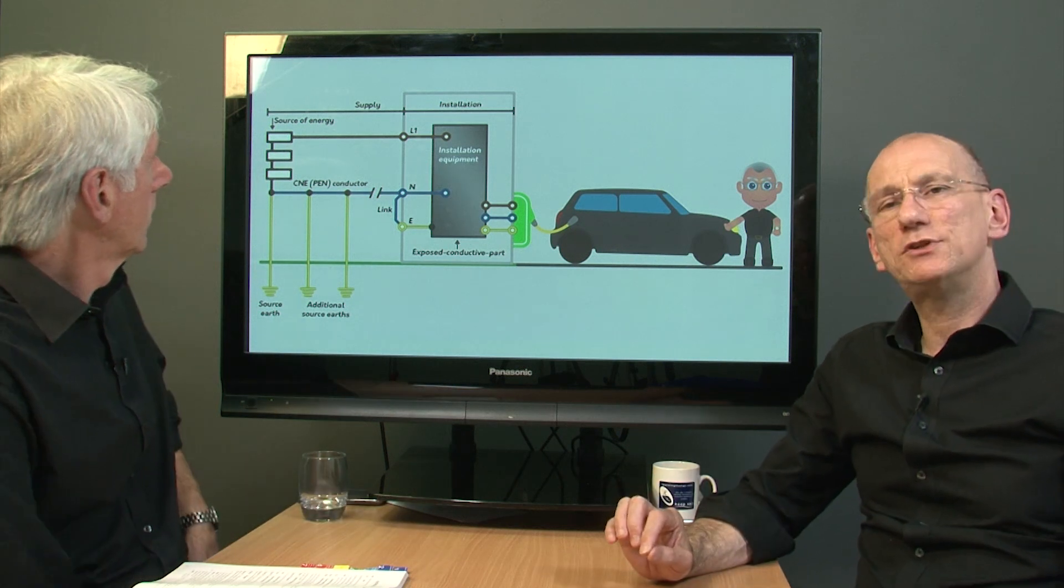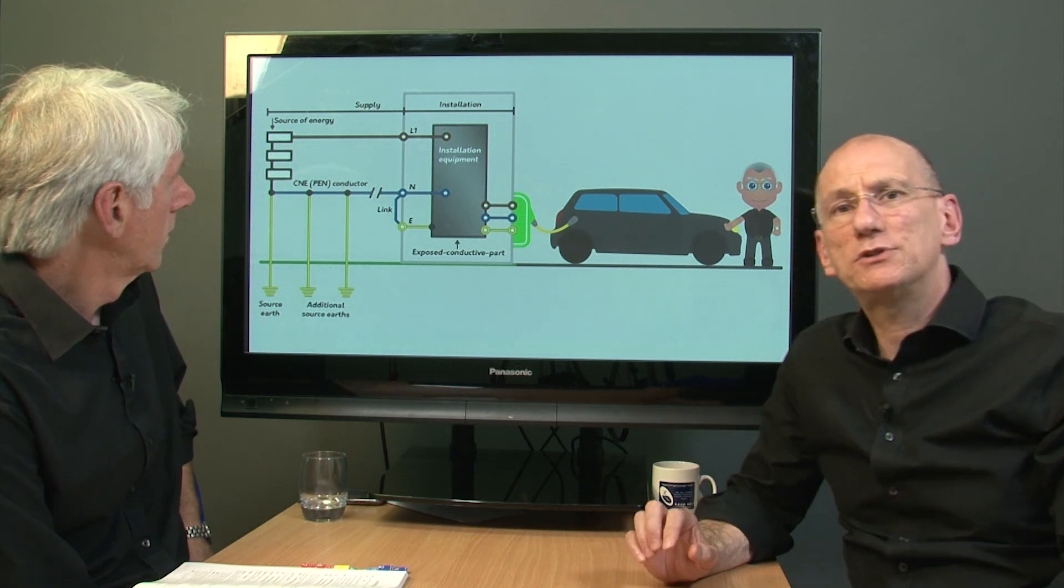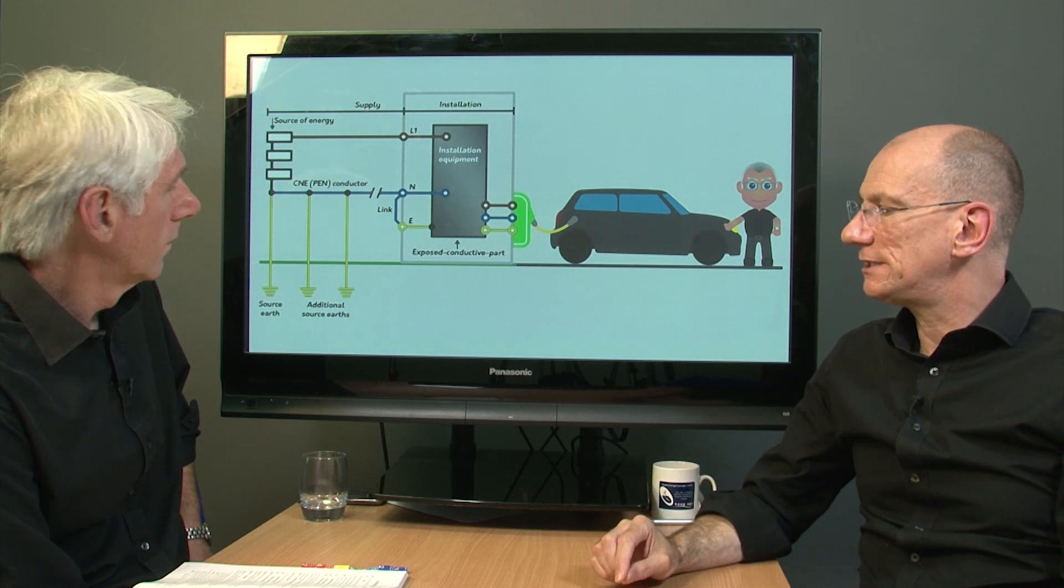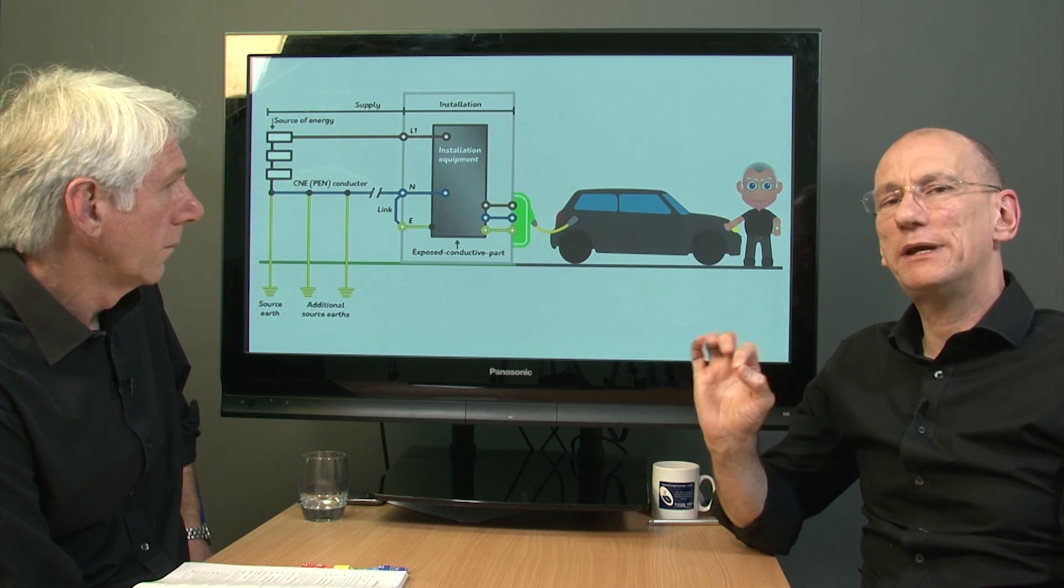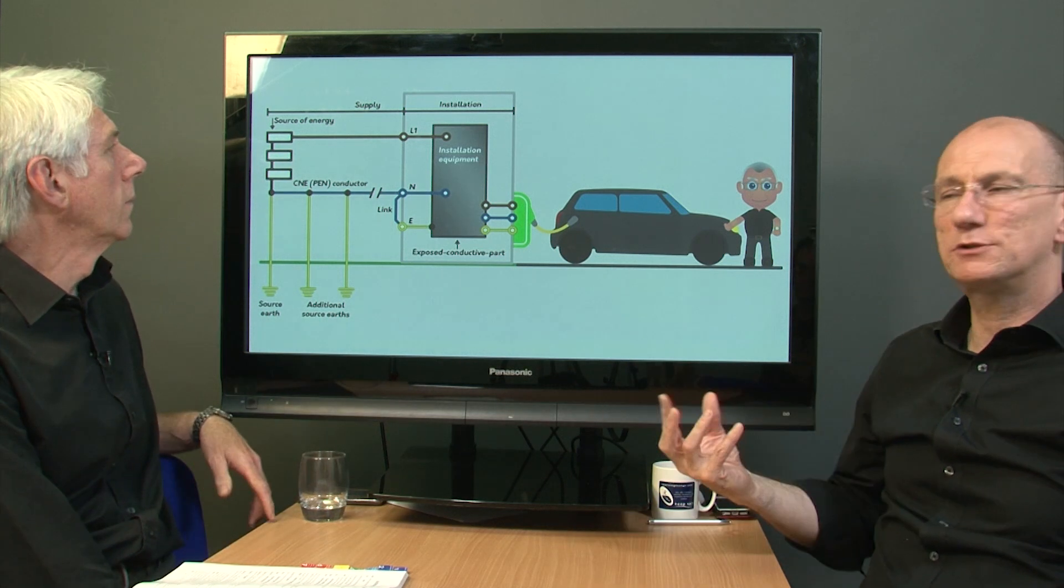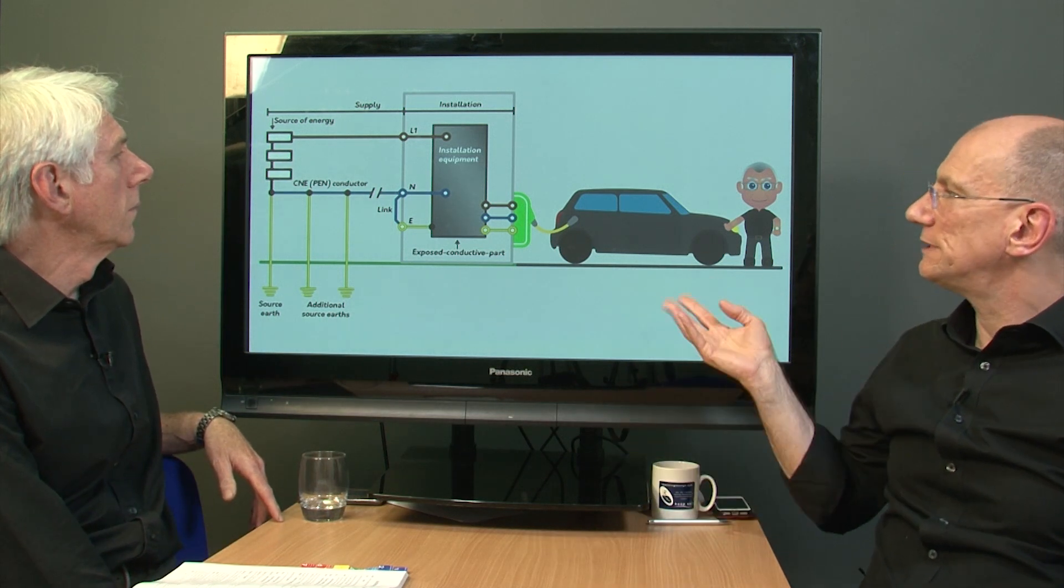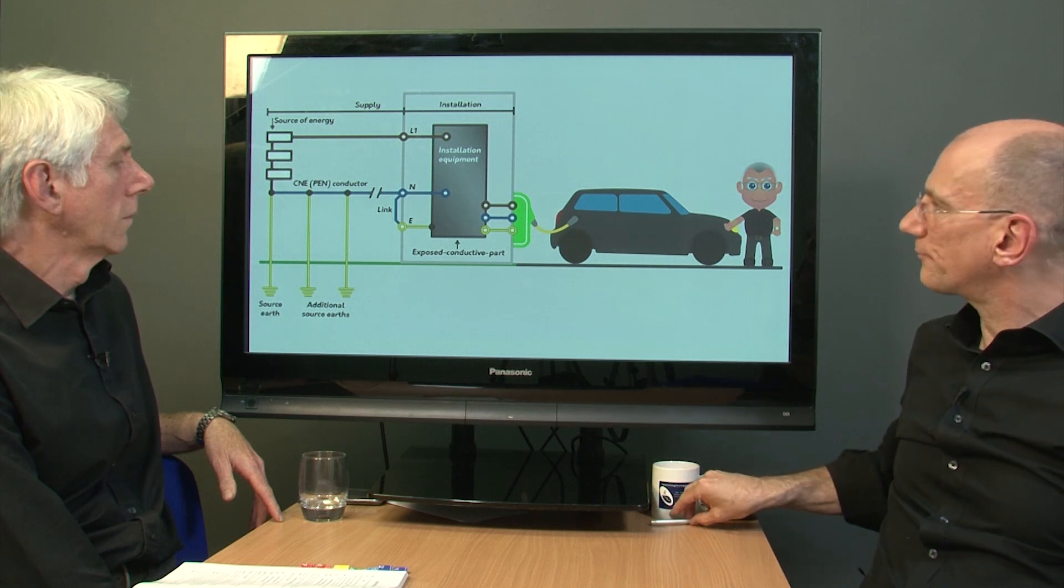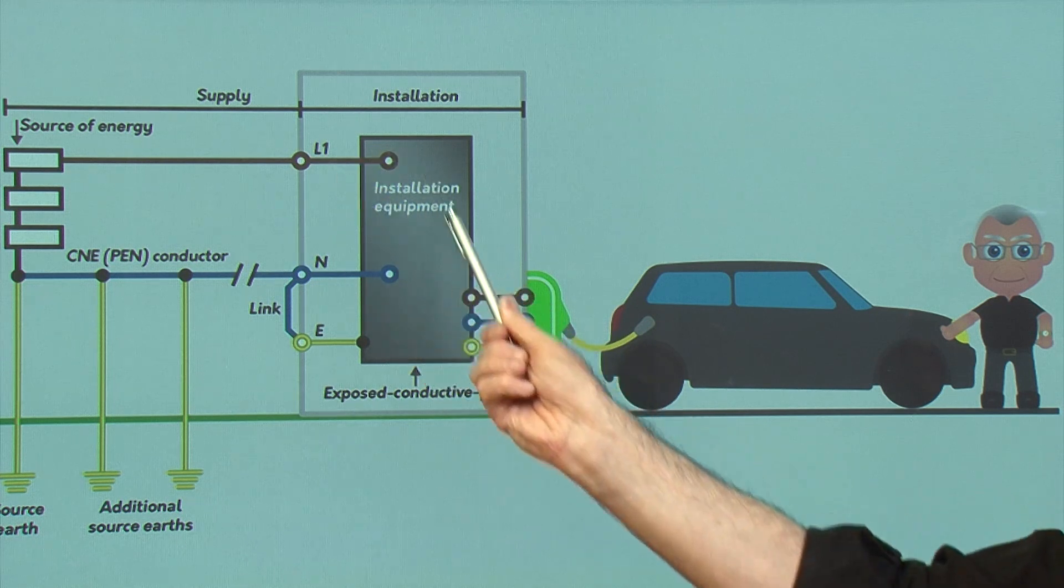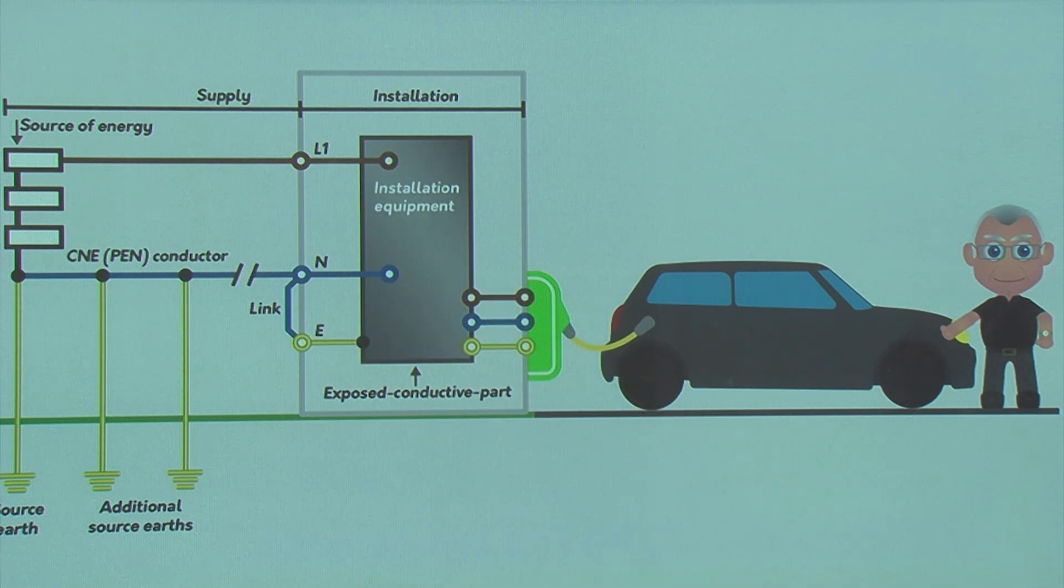In section 722, which covers electrical vehicle charging points, there's a particular point made about TN systems, and in particular a PME scenario, and why there is a risk. Now this isn't spelt out in the requirements, but this is a nice little picture to explain it. So, basically, we have our supply coming into the installation, and obviously a return path there via the neutral, via the pen conductor. Now that pen conductor is an earth and a neutral, so it's combined.